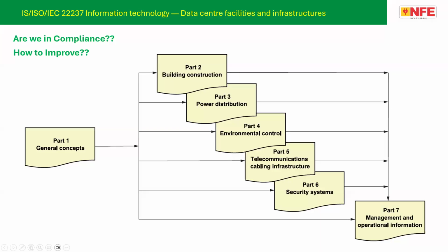But when we ask how the ground fault current will flow, then they are saying that yes, the current first goes to the PE conductor, then it will go to the soil, and then it will come back. Some are saying that it will come back, and some are saying that no, it will get dissipated within the soil. So this is the challenge we are facing from the consultant side actually, and their assumption is that if we connect the PE with neutral, then something wrong will happen with the conductor.